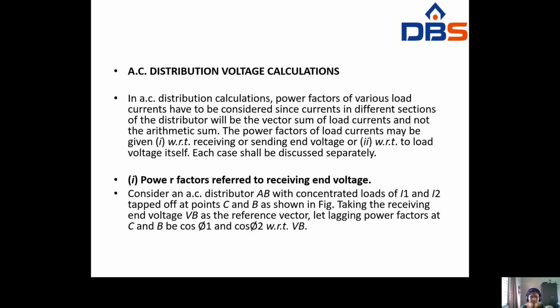AC distribution voltage calculation. In AC distribution calculations, the power factors of various load currents have to be considered, since the currents in the different sections of the distributor will be the vector sum of the load currents and not the arithmetic sum. So here you have to add all the current values as a vector sum.